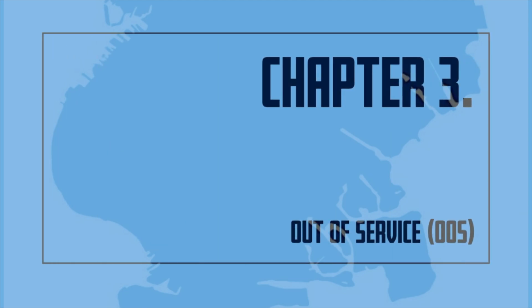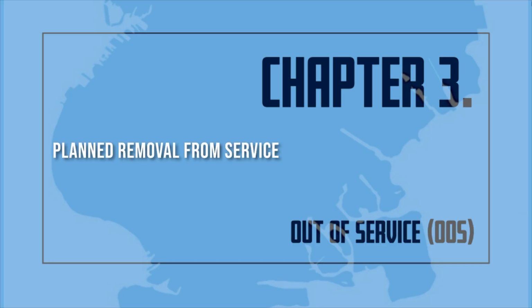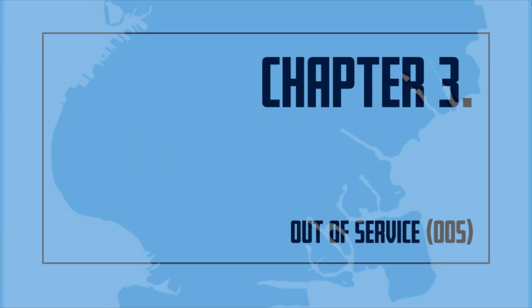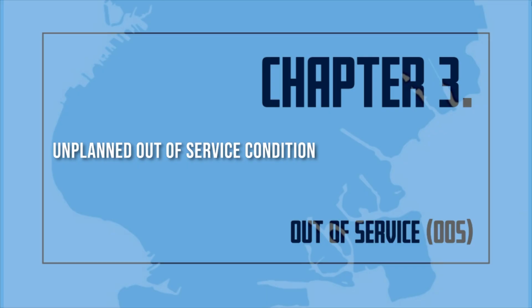Chapter 3. Out-of-service systems. Planned removal from service. When the system or a portion of the sprinkler system is placed out of service for a scheduled inspection, testing, regular maintenance, minor repairs, or for construction affecting not more than 1 floor, the certificate of fitness holder and the impairment coordinator shall be made aware of and authorize the placing of the system out of service. Unplanned out-of-service condition. A serious defect in the sprinkler system including, but not limited to, an empty tank, a break or major leak in the system's water piping, inoperative or shut water supply valves, defective fire department connections, construction-related shutdowns affecting more than 1 floor, or complete or partial shutdowns of the sprinkler system other than a shutdown for a planned removal from service.